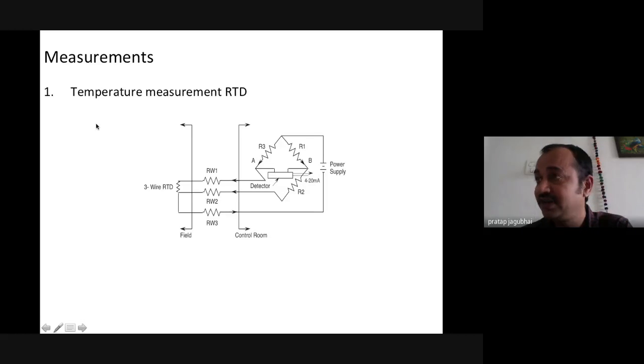So another important thing is the RTD, resistance temperature detection. So RTD is very widely used to measure the temperature, and can be cited as a PT100, which is basically made from platinum material. PT100 is the indication that at 0 degree centigrade temperature, 100 ohm resistance will be available. Similarly, there is PT1000: at 0 degree centigrade, 1000 ohm resistance will be available, and this will be taken in the form of a Wheatstone bridge, where the RTD is connected through the wire and will be taken in one arm of the Wheatstone bridge, where you can say R1 into R4 equal to R3 into R2.